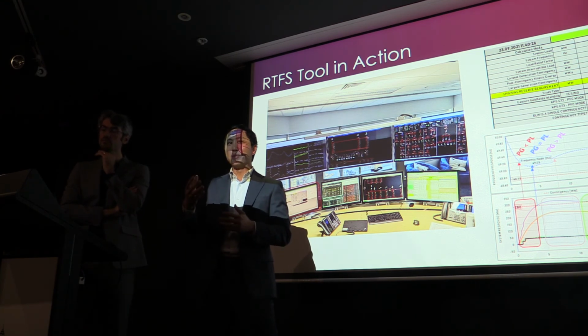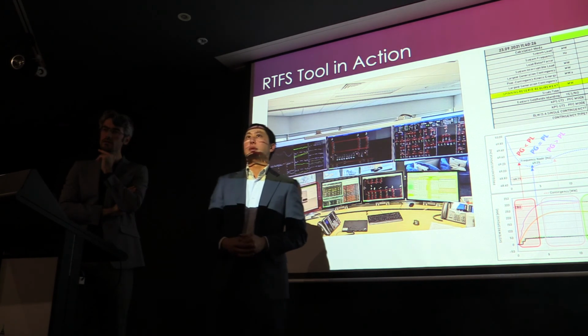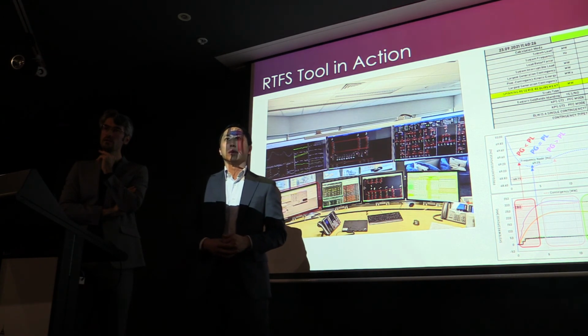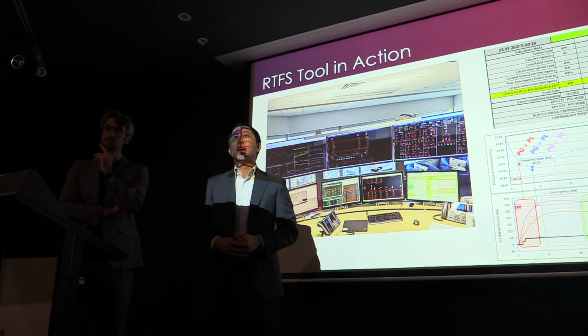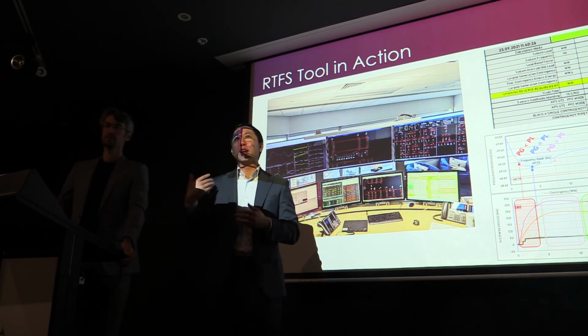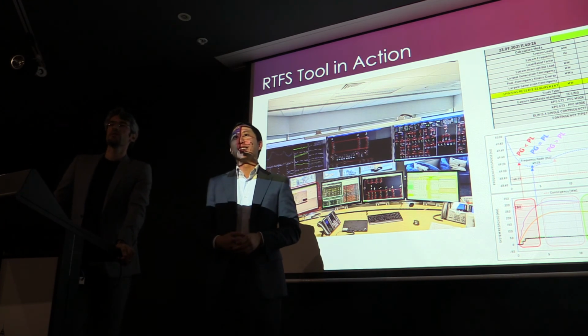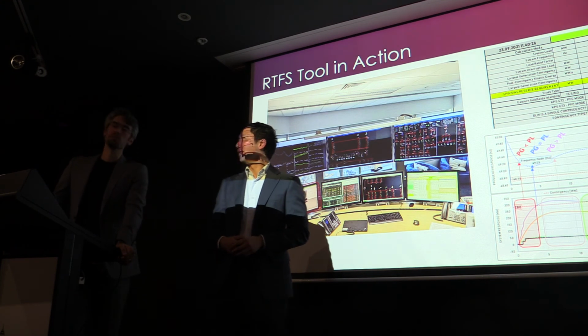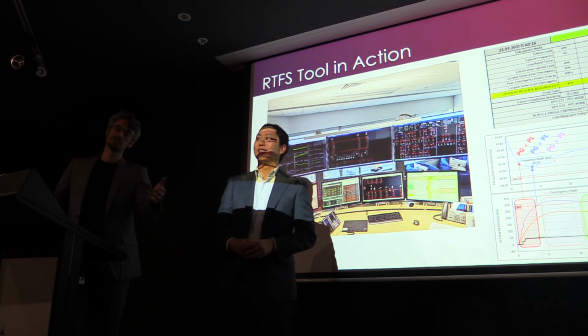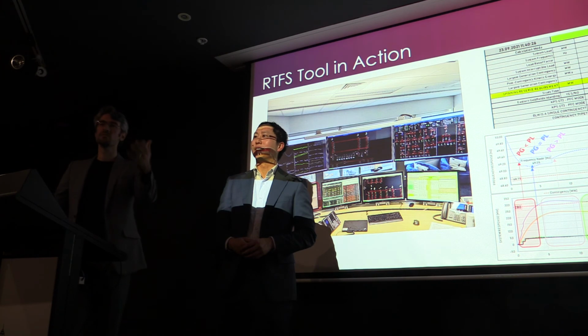So yes, but in principle, if you want everything to have virtual inertia, then you probably need to back off a little bit or oversize your inverter. It also depends how much energy you can get from the solar panels. Yeah, so you're right, this is mainly for battery-backed systems. So the energy should be there, whereas in synchronous generators we get it from rotating mass. Exactly.